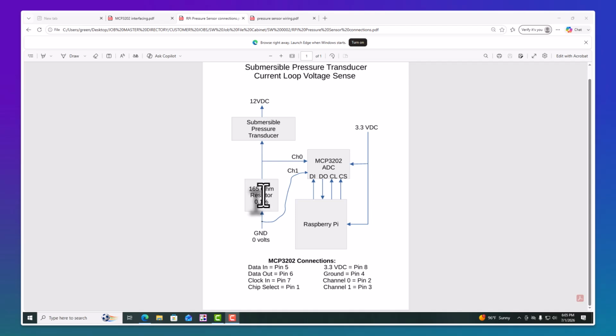I calculated this with the pressure transducer having 12 volts across its outputs. The current is what's controlled, and it outputs from 4 milliamps to 20 milliamps.